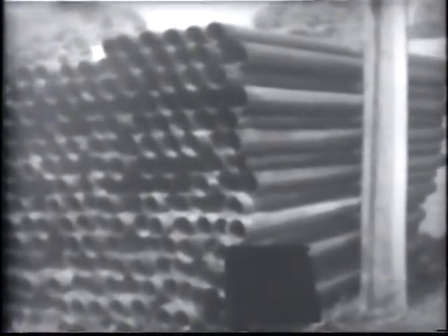We used to use a fiber coupling, which is made out of the same material as the conduit, but these conduit are not always perfectly round, and by using those fiber couplings, unless you painted the joints, there was a chance of the concrete seeping through these joints, because when you pour this concrete, it's usually fairly wet. These plastic couplings pretty well conform to the conduit, even though they may be a little out of round. So they worked out a lot better.